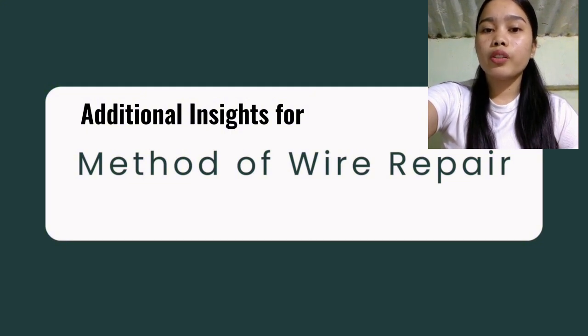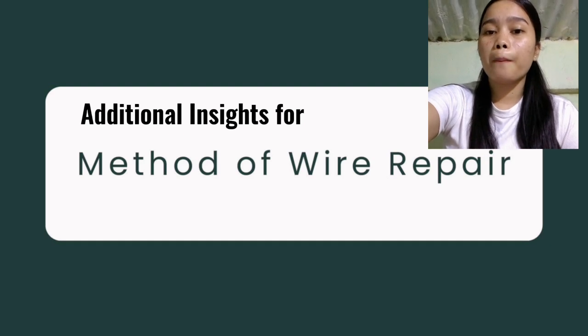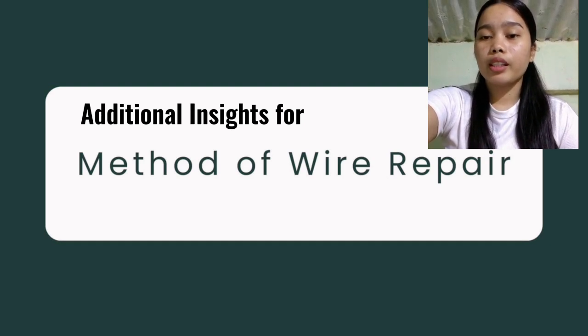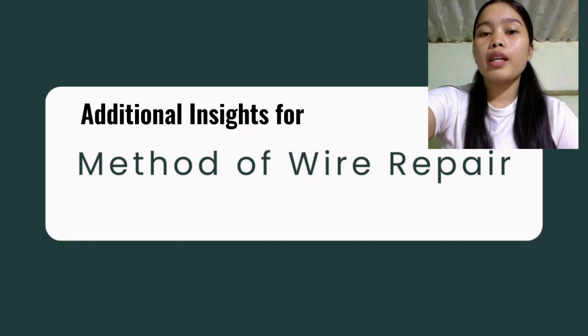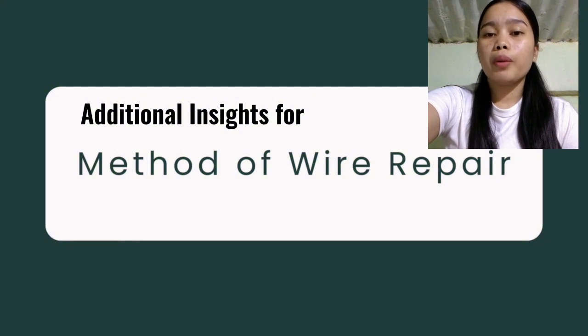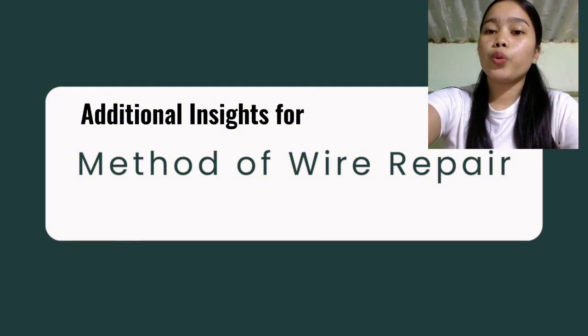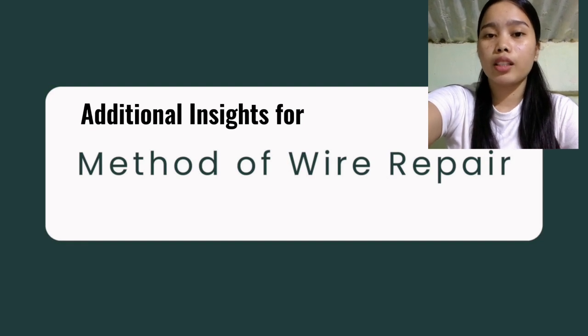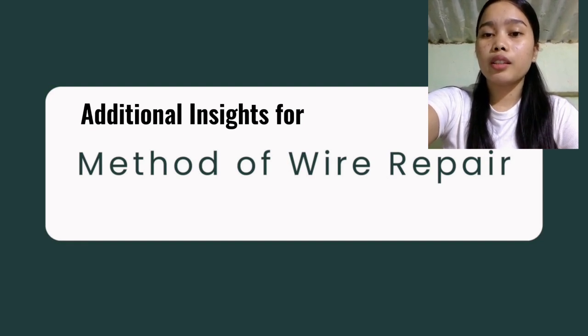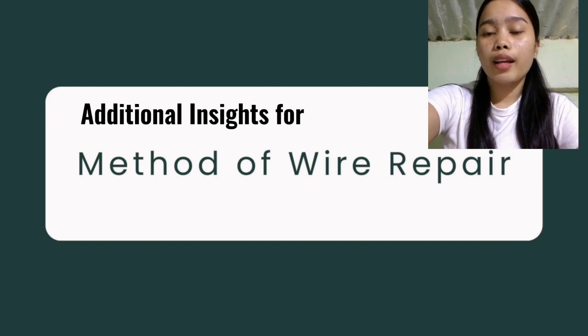And for corrosion resistance, both crimp and solder methods can achieve corrosion resistance when combined with appropriate sealing techniques such as adhesive-lined heat shrink tubing. For the best practices for optimal results, it's recommended to use high quality connectors and materials. Ensure proper installation techniques and consider the specific application's requirements such as exposure to movement, moisture, and temperature variations.